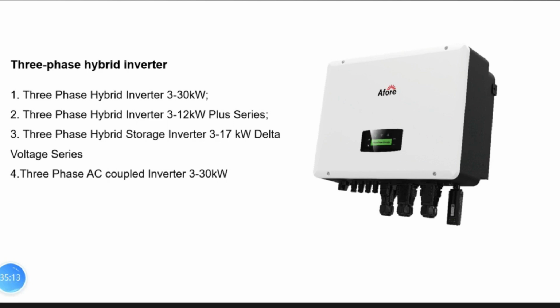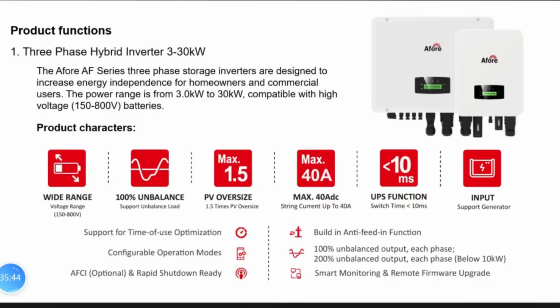Another series is the 3 up to 17K Delta version. The delta voltage version works for the American or North European markets, where they have the low voltage three-phase 230 grid. And the later series is the AC coupled one, with power size from 3 up to 30. So when we go through all the features of the three-phase inverters, all of the three-phase models have an IP65 protection level, and a maximum of 1.5 times the PV size capacity.